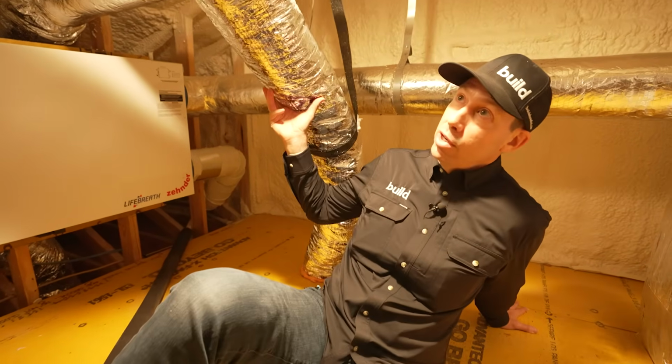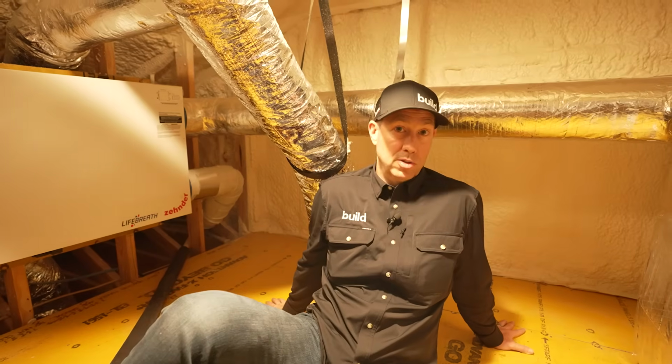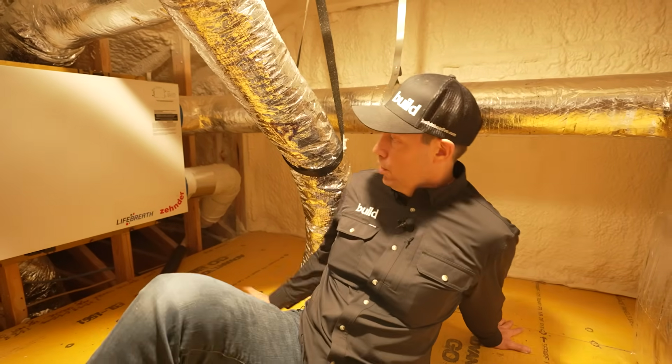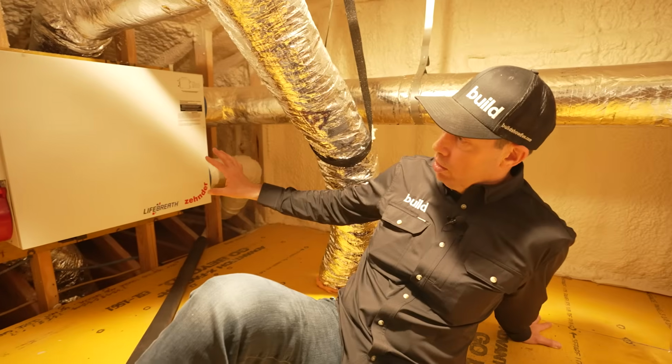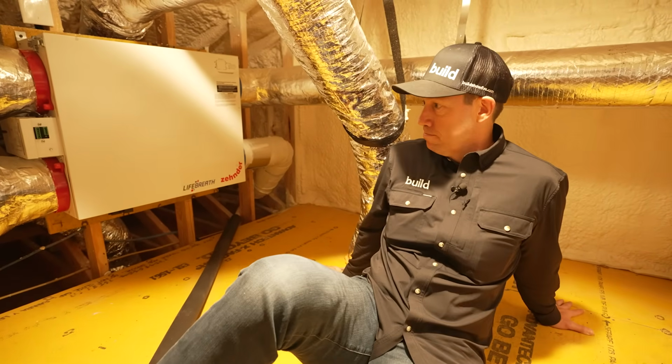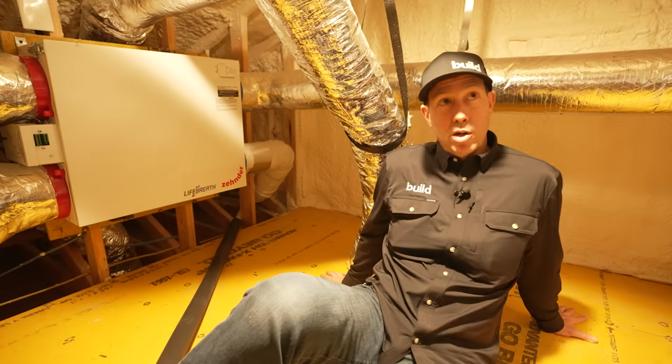They should have all the ducts in the same air conditioned space that you live in. And we should have supplemental dehumidification. And we should have a whole separate unit, including separate ducting if we're going to do best practice for fresh air. The last thing I want to mention up here, we use trusses.